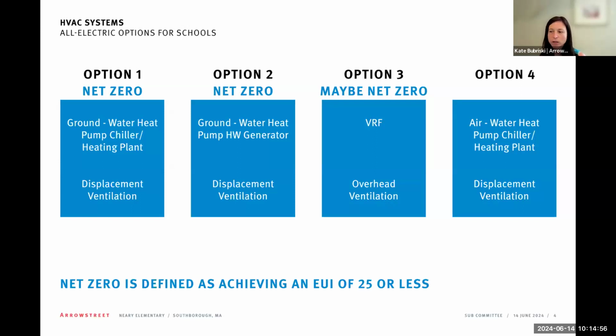The real difference between option 1 and 2 is option 1 is a ground source heat pump chiller heating plant. And basically that's distributing both hot water and chilled water through the building. And so you can achieve full cooling, which is essentially a 75-degree set point, where option 2 is using a heat pump hot water generator. So it's for generating hot water. And then the ground loop is not producing chilled water. So the ground loop is going to air handlers and helping to produce dehumidified cooled air. But the set point there would be 78 degrees. So it's not what we call full cooling. And that's the main difference between 1 and 2. Why you might do 2 versus 1, I would say the majority of projects are option 1 that are doing ground source.